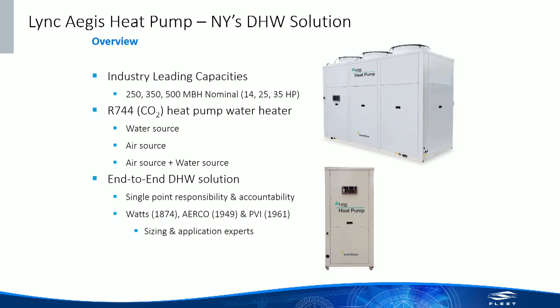So Watts and Lync made the decision to make sure that they can provide an end-to-end solution. They want to treat this product as any other water heater: bring cold water in, hot water after the mixing valve out. Everything in between is provided and designed by Watts, by Lync, by GA Fleet here in New York. And we were able to lean on that history of Watts, AERCO, PVI, to really take advantage of their expertise in domestic hot water sizing to get more aggressive sizings than your typical ASPE or ASHRAE curves, Hunter curves, things like that.